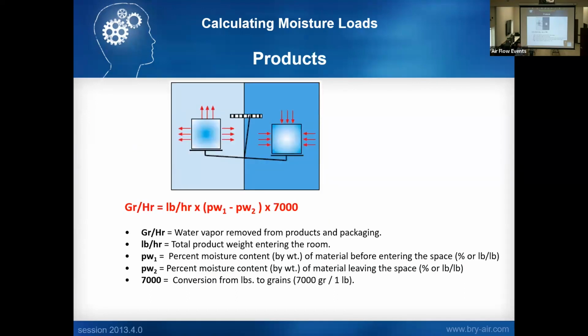Again, we talked about product. So if you're doing meat drying, sausage drying, those types of applications, poultry, where your product's coming in at a certain weight, you need to dry it down to a certain weight. That amount of moisture being dried from that product is a load that needs to be accounted for. Basically we're looking for the weight of the product coming in, the weight of it when it's dry and you can use it, and then how many pounds of product you want to do in an hour period. And that's how we calculate that load.